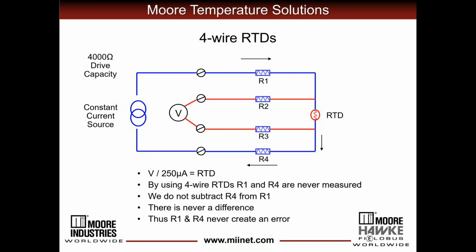Now, I did a little calculation yesterday on how much resistance there would be in wire cable. And standard instrument cable comes out to be essentially 40 miles of cable. So the only reason you would have a problem is if you had 40 miles of cabling between your sensor and your measuring device. And of course, that could be 20 because of the 2 wires. So there you go.